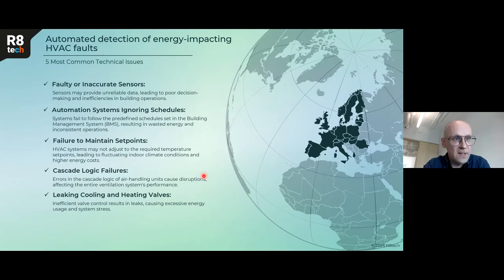One slide about faults. All the buildings which have BMS have their own BMS alarm system. And here we are putting the 5 most common technical issues, which we see in basically every building, more or less. Inaccurate sensors. If the sensor is showing unreliable numbers, then usually this is detected by the BMS as well. But sometimes it shows static values, or for example, a CO2 sensor is showing unrealistic numbers or needs calibration. We will detect these issues as well.